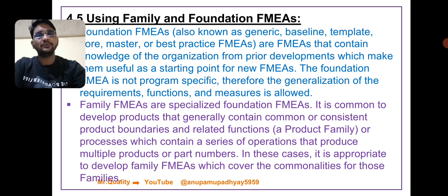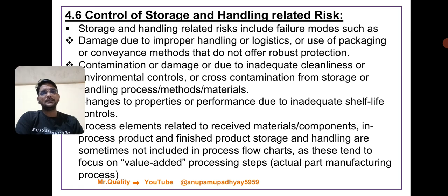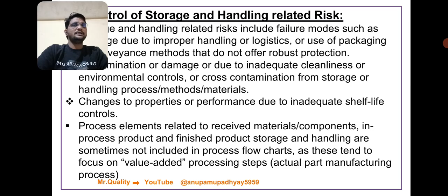Next is control of storage and handling related risk. Storage and handling related risk includes failure modes such as damage due to improper handling or logistics, or use of packaging or conveyance methods that do not offer robust protection. Contamination or damage due to inadequate cleaning or environmental control, or contamination from storage or handling process, method or material. It also means changes to properties or performance due to inadequate shelf-life control. Process elements related to receiving material, components, in-process product and finished product storage and handling are sometimes not included in the process flow chart, as these tend to focus on value-added processing steps, the actual part manufacturing processes.